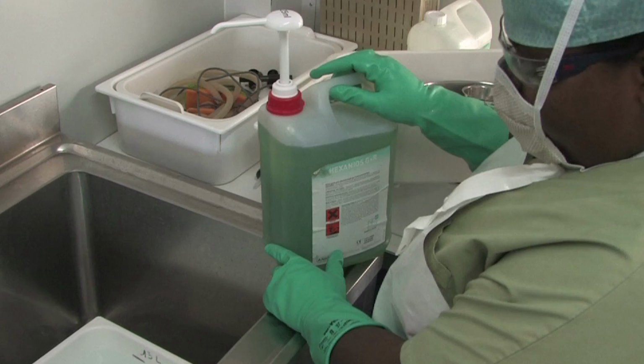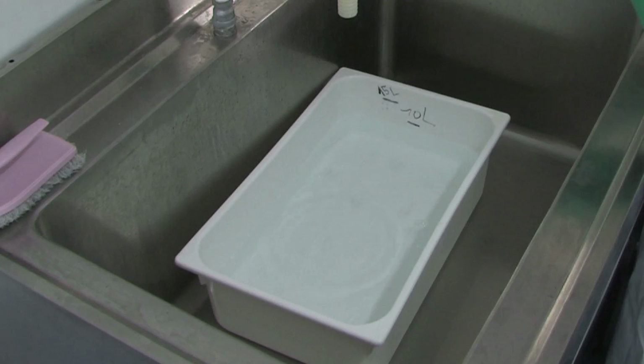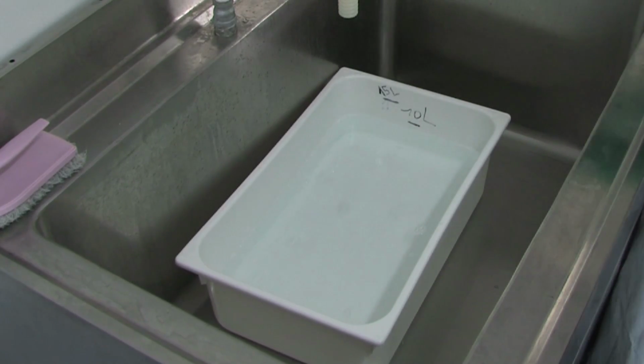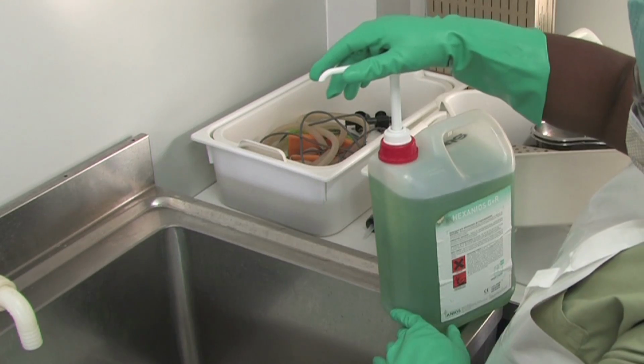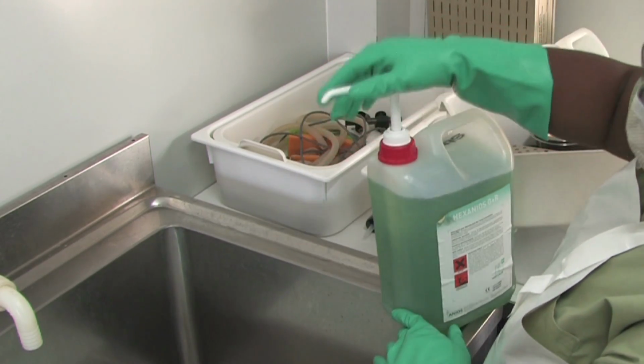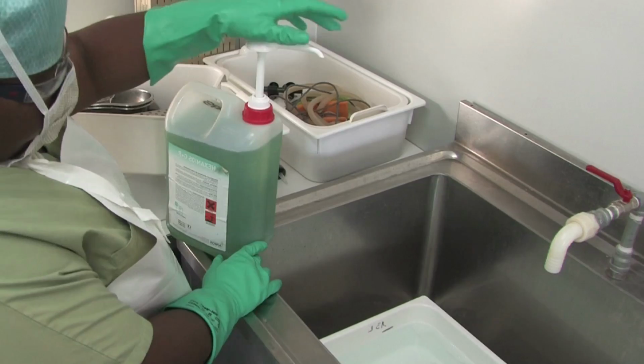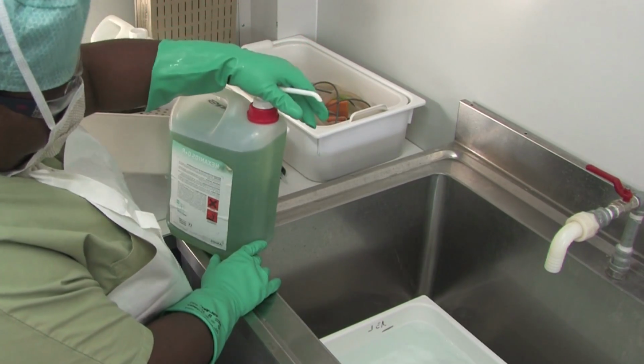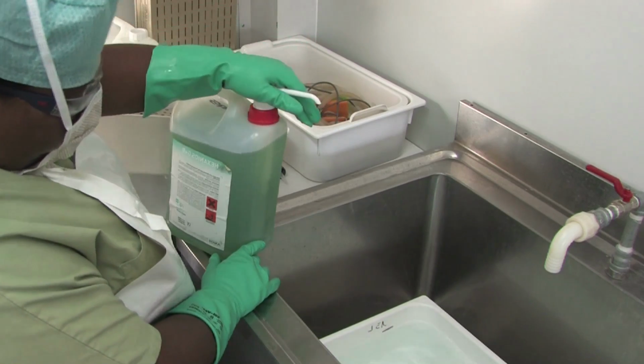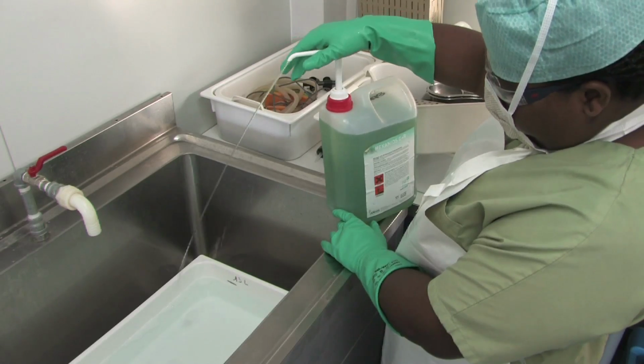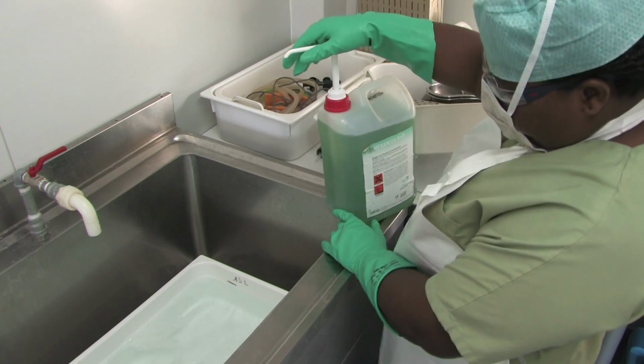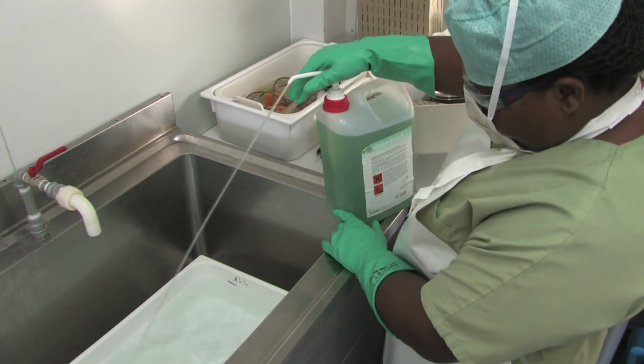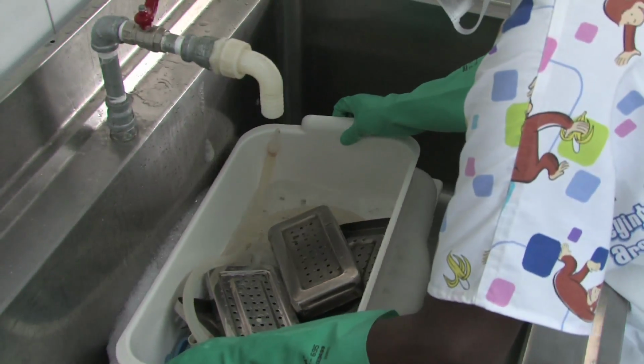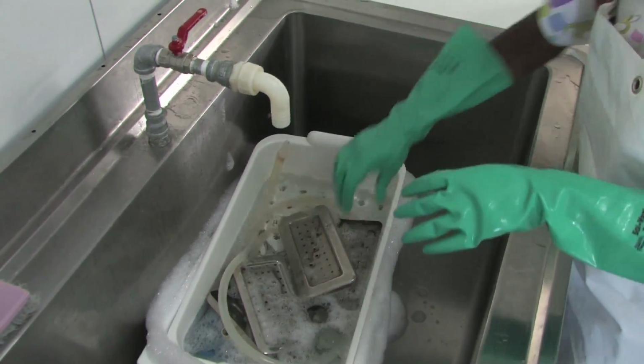Add the detergent disinfectant solution, using the appropriate amount for the desired volume of water: 25 milliliters of product, or 1 push on the dispenser pump, for 5 liters of water; 2 pushes, or 50 milliliters of product, for 10 liters of water; or 3 pushes, that is 75 milliliters of product, for 15 liters of water. Continue filling to the desired volume of water. Allow enough water to completely cover the instruments.